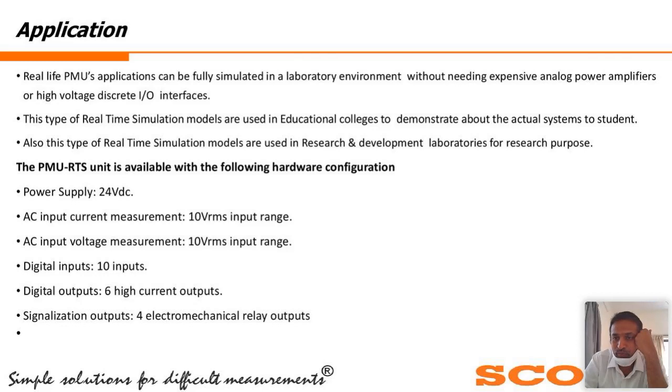Okay, so again, Mr. Punuswamy asks whether the PMU can get instructions from the central command, or only one way from PMU to PDC. No. PDC and PMU have both ways: taking the data and sending the data to the PDC, and if any decision is taken by the PDC or software, it will send the control command to the PMU, and the PMU has the digital output. So it takes the command and acts based on the command. So it's a two-way communication.